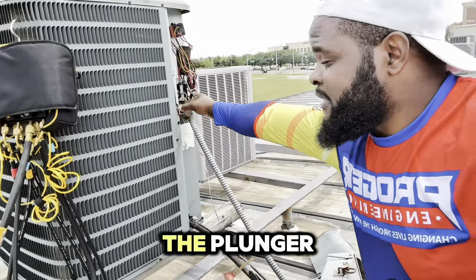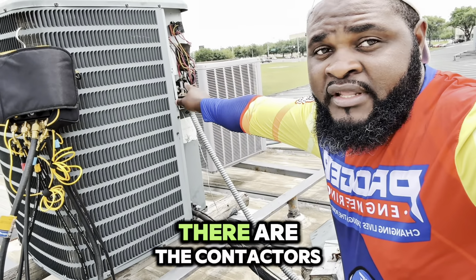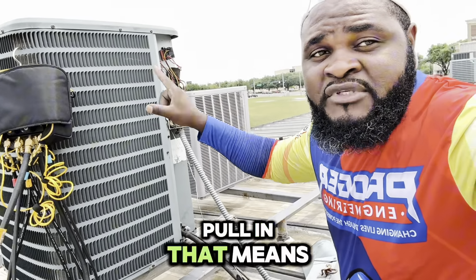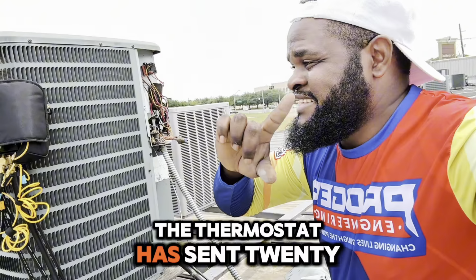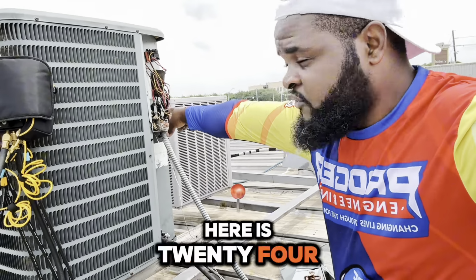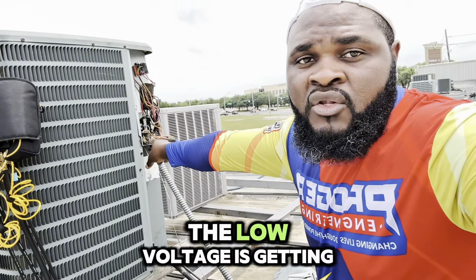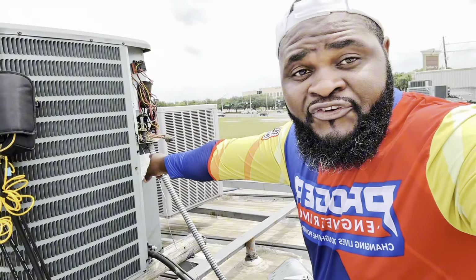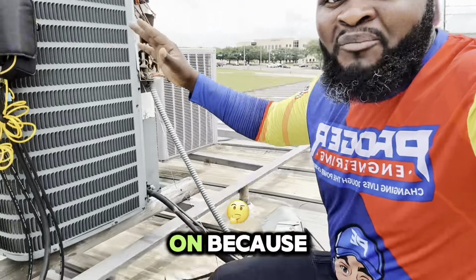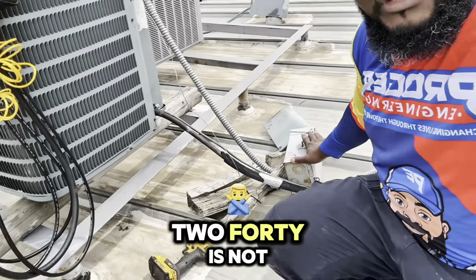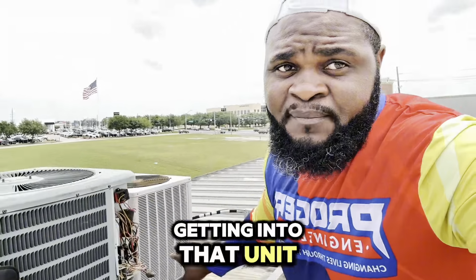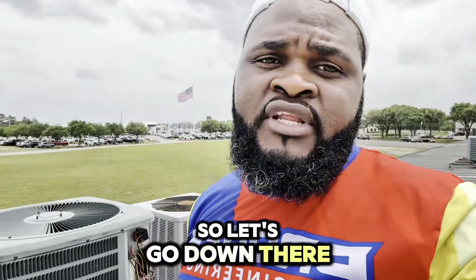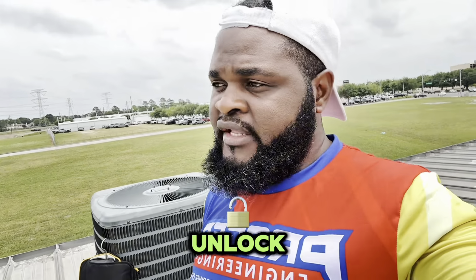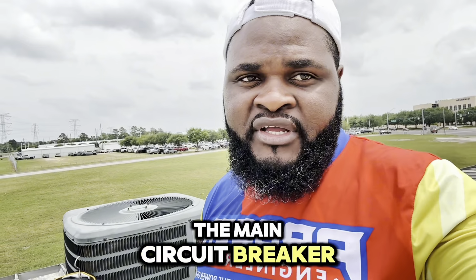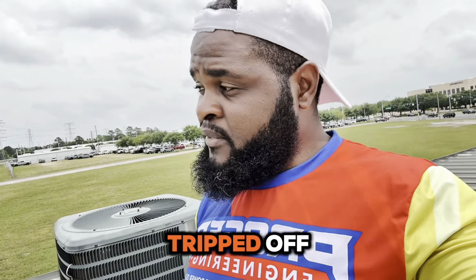But at this point, the plunger there at the contactor has pulled in. That means the thermostat has sent 24 volt here. It's 24 volt getting in here. The low voltage is getting in here, but it will not power on because 240 is not getting into that unit. So let's go down there and locate the main circuit breaker and see if it's tripped off.